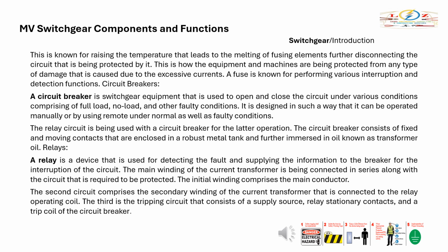Relays. A relay is a device that is used for detecting the fault and supplying the information to the breaker for the interruption of the circuit. The main winding of the current transformer is connected in series with the circuit that is required to be protected. The initial winding comprises the main conductor. The second circuit comprises the secondary winding of the current transformer that is connected to the relay operating coil. The third is the tripping circuit that consists of a supply source, relay stationary contacts, and a trip coil of the circuit breaker.